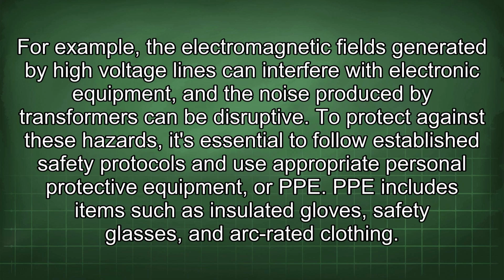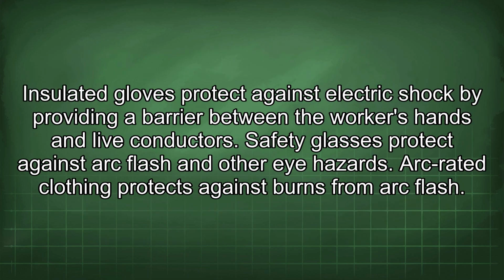For example, the electromagnetic fields generated by high-voltage lines can interfere with electronic equipment, and the noise produced by transformers can be disruptive. To protect against these hazards, it's essential to follow established safety protocols and use appropriate personal protective equipment, or PPE. PPE includes items such as insulated gloves, safety glasses, and arc-rated clothing. Insulated gloves protect against electric shock by providing a barrier between the worker's hands and live conductors. Safety glasses protect against arc flash and other eye hazards. Arc-rated clothing protects against burns from arc flash.